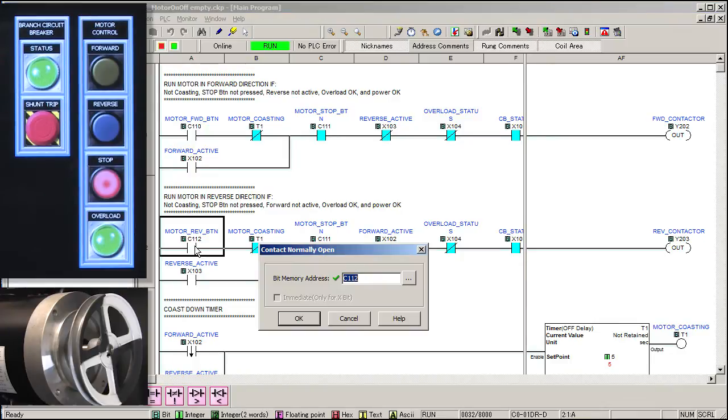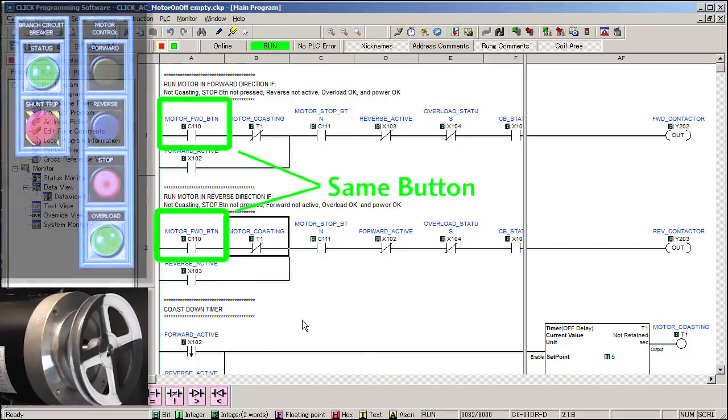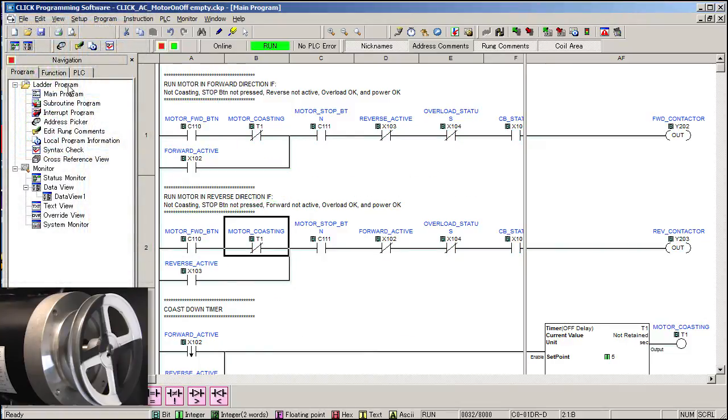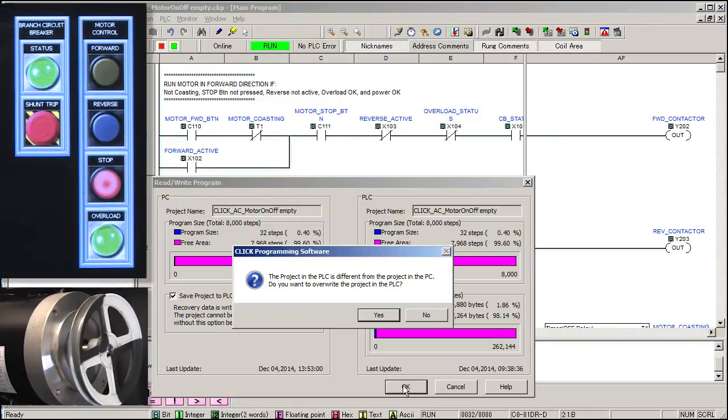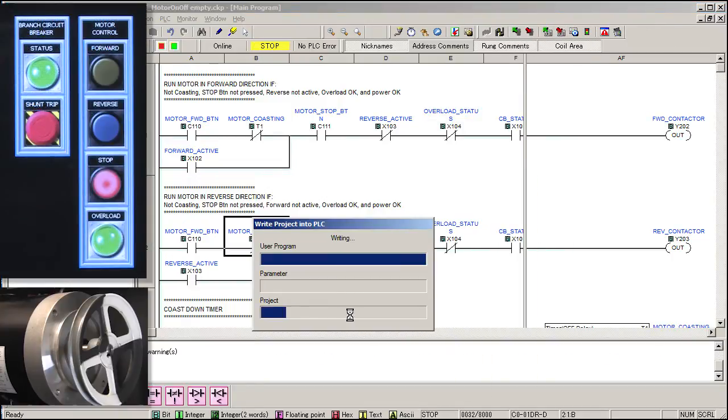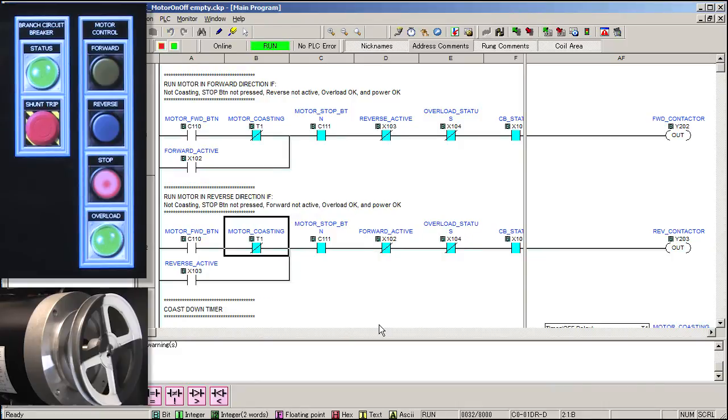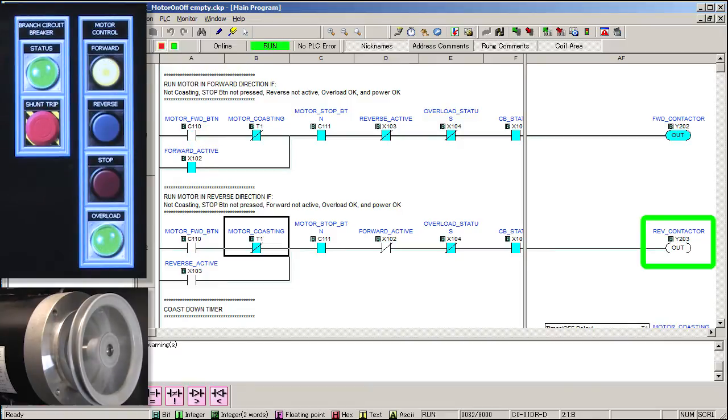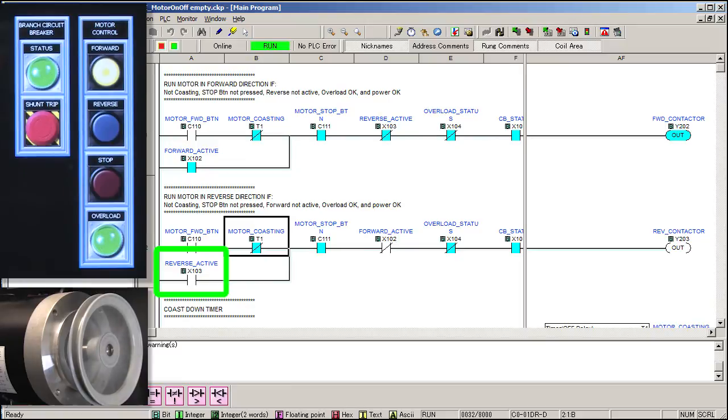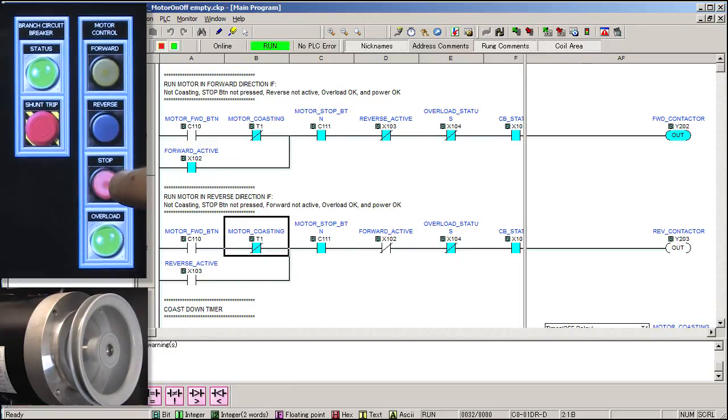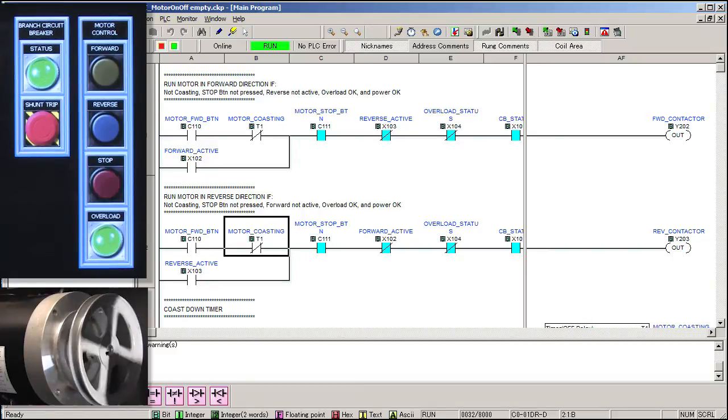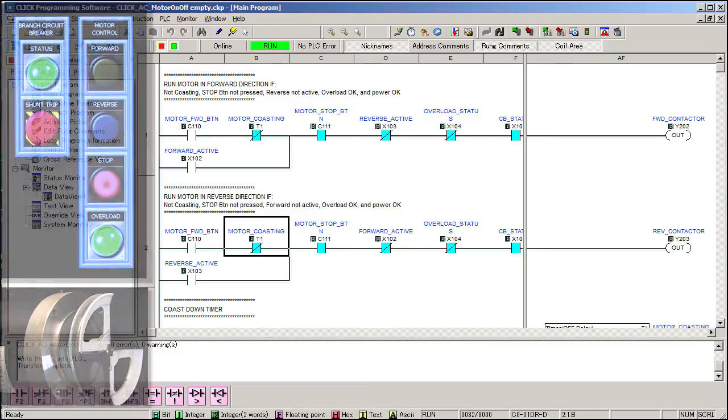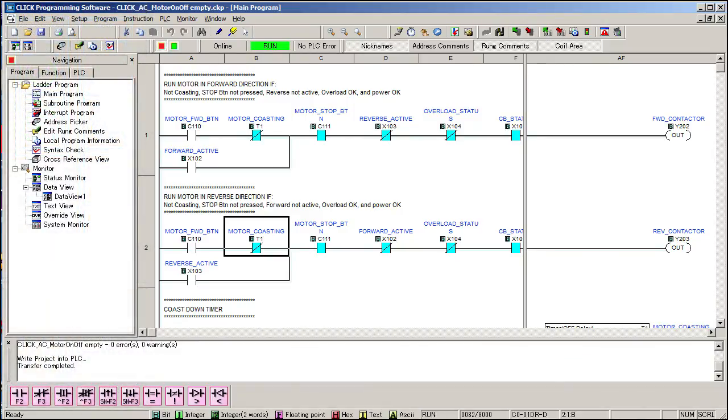Let's prove it. Let's engage both contactors on the same forward button press. Now, they are guaranteed to start at exactly the same time. Save that change and write it out to the PLC. Sure enough, if we press the forward button, both circuits light up, but then the reverse circuit turns back off because the mechanical interlock wouldn't allow the reverse AUX contact to close. So now you see why it was so important to add that extra mechanical interlock in the hardware video. And since it's just snapped into place and it's only $2.50, why wouldn't you add the extra insurance to make sure you have an idiot proof super reliable system?